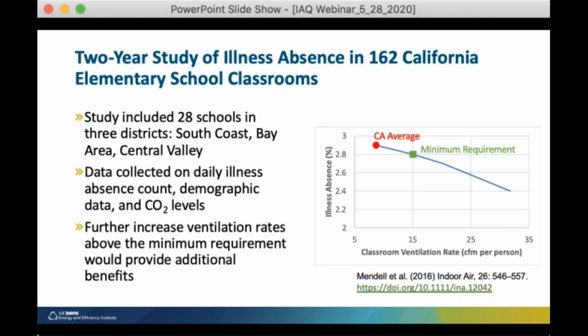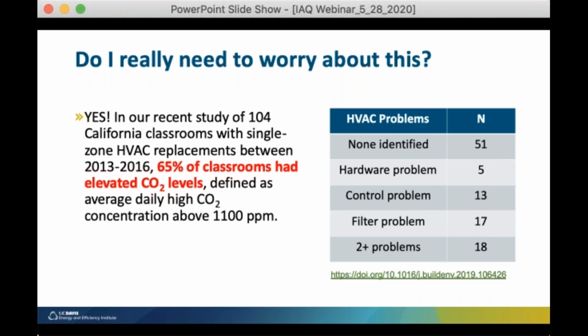The study found that all 3 school districts had a median ventilation rate below standard. Increasing the ventilation rate from the current 4 liters per second per person, or about 8 or so CFM per person, to the minimum requirement of 15 would reduce illness absence among students. And further increasing ventilation rate would provide additional benefits. So you may say, this is great research, thanks for sharing, but that's not my school. We have HVACs, like the ones you show, and it turns on, it heats and cools, so things are working fine. I don't have to worry about this.